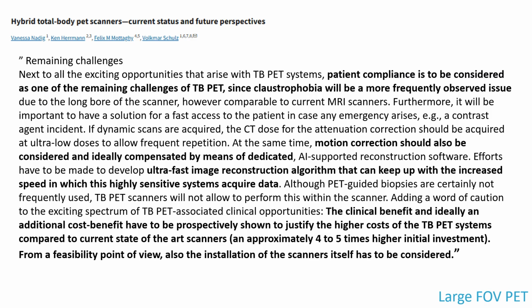Some remaining challenges have to be considered also for the hybrid total body PET scanner. First of all, patient compliance, because claustrophobia will be a more frequently observed issue with this kind of scanner. Motion correction is not completely a solved problem. We need very fast image reconstruction algorithms, as we have to manage a very huge quantity of data.